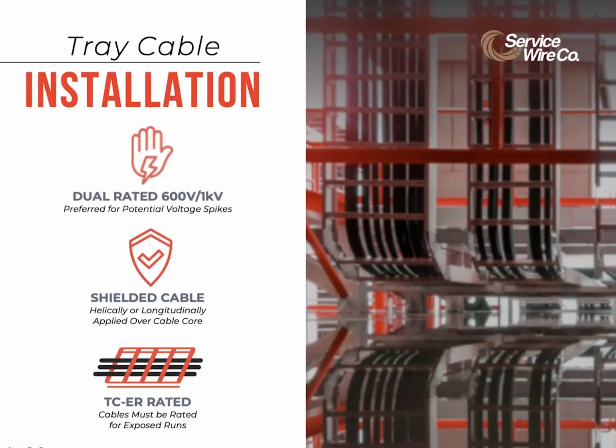Looking for traditional tray cable instead? Service Wire has that too. We were one of the first manufacturers to offer UL 1277 approved 600 volt 1 kV dual rated tray cable. Dual rated tray cable is a more robust product. It is a cost-effective alternative for applications that require a lower voltage cable but are at risk for potential voltage spikes. For example, 1 kV rated tray cable can withstand greater electrical adversity, have a lesser impact during a disruptive event, and the recovery time is faster than a less resilient system.